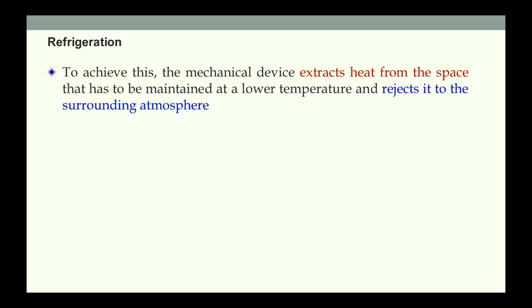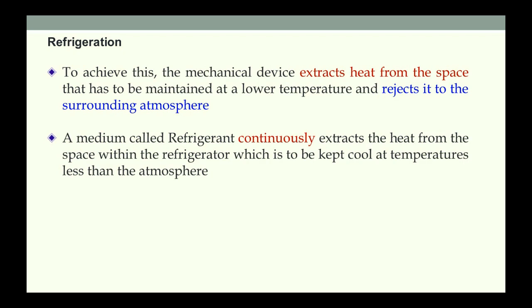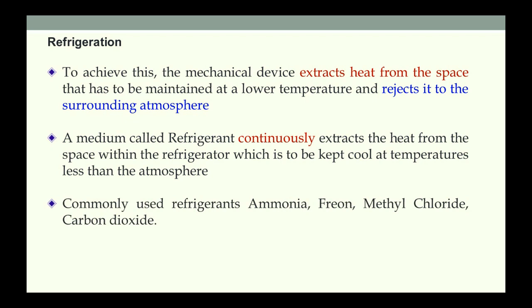In VCR, that is vapor compression refrigeration system, a mechanical device extracts heat from the space that has to be maintained at a lower temperature and rejects it to the surrounding atmosphere. A medium called refrigerant continuously extracts heat from the space within the refrigerator to be kept cool at temperatures less than atmosphere. Commonly used refrigerants are ammonia, freon, methyl chloride, and carbon dioxide. Nowadays, environment-friendly hydrocarbons like propane R290 and isobutane R600A are used.